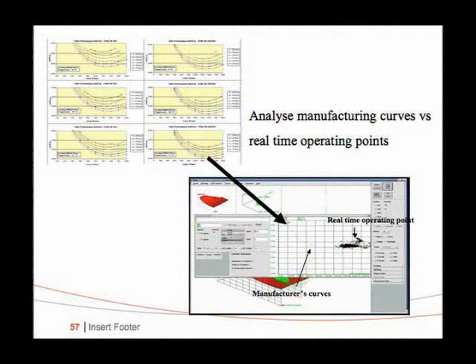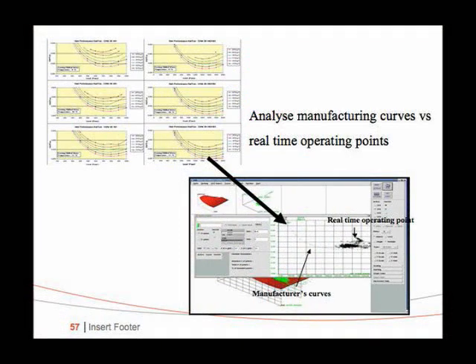In order to cut cost, you use one of these Annubar pitot tube devices that deal with pressure drop. When you're running 10,000 tons of chiller plant, I think you can afford a 0.5% magnetic meter. So the approach is quite straightforward. We just do fundamental engineering, go back, get all the curves at part loads, and you drive the salespeople crazy because nobody ever asked for printouts at different flow rates, different temperatures, etc. And then you compare it to our data acquisition set up on site, and it is far out from the manufacturer's claims.